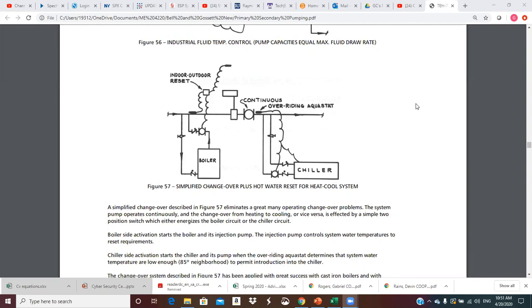We talked about figure 56 in the previous lecture. So we're on to figure 57, which is a simplified changeover that eliminates a great many operating changeover problems. Changeover refers to a two-pipe system — in the wintertime we circulate hot water, and in the summer we circulate chilled water through the same pipes. All the air handlers just have one coil, whether a fan coil unit or unit vent. The fan blows across it, getting hot water when it's cold outside and chilled water when it's hot outside.